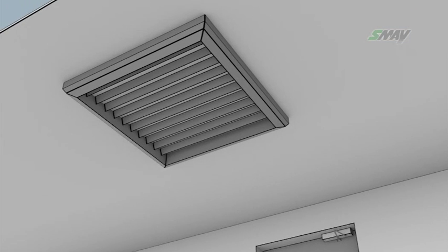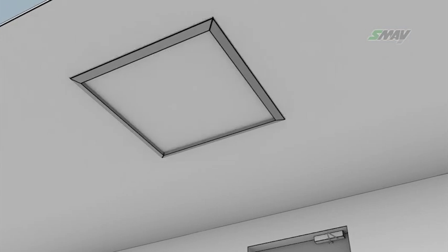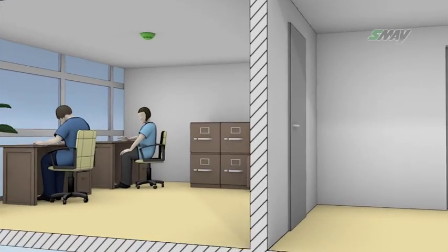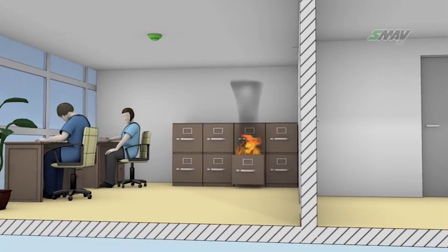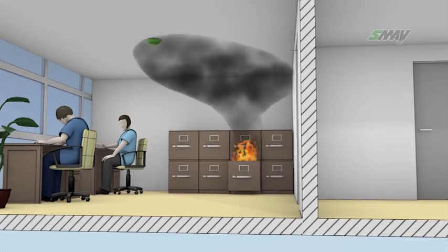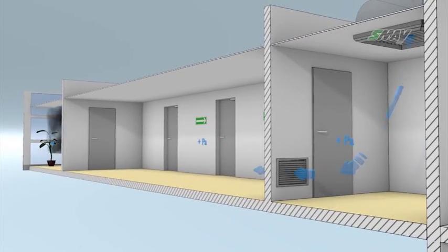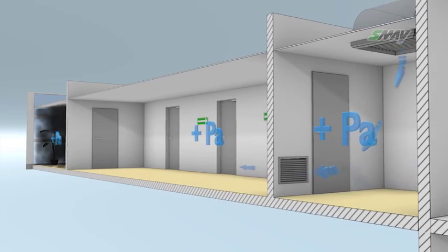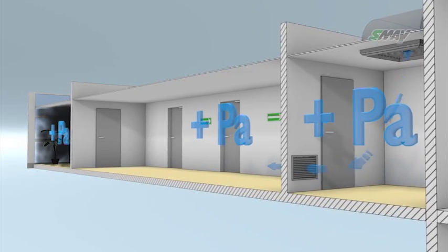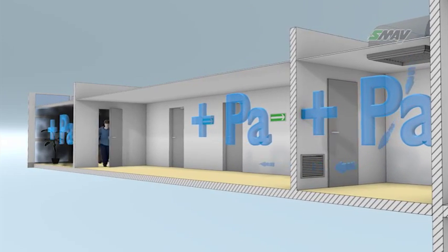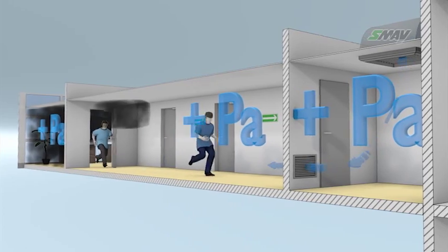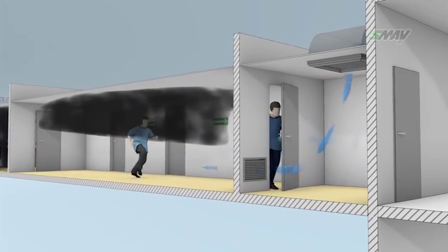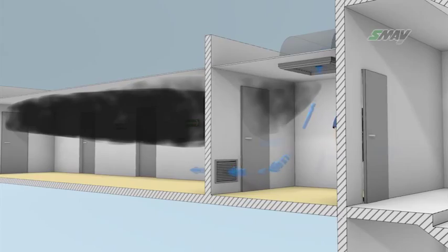In order for the installation to function properly, correct air release should be ensured. If the designer does not pay attention to this detail, operation of the lobby air supply installation will cause overpressure, both in the lobby itself and in the adjacent corridor. Then, during evacuation from premises on fire, smoke will easily penetrate the corridor and subsequently into the lobby. It could also result in the stairwell being filled with smoke.